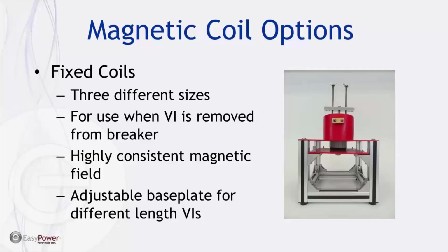It's highly consistent, whereas with the flex coil, there is some possibility of human error, of not wrapping the coil in the exact same place, which doesn't give a very large change in the result, but it's just not as consistent as this fixed coil could be. And these have adjustable bases so that you can adjust them for different length vacuum interrupters, because you do want to place the magnetic field around where the contacts of the vacuum interrupter are.